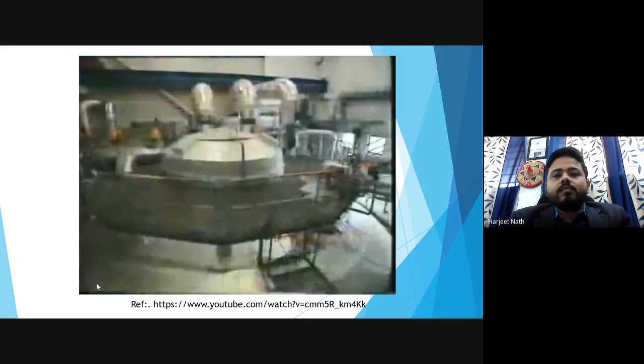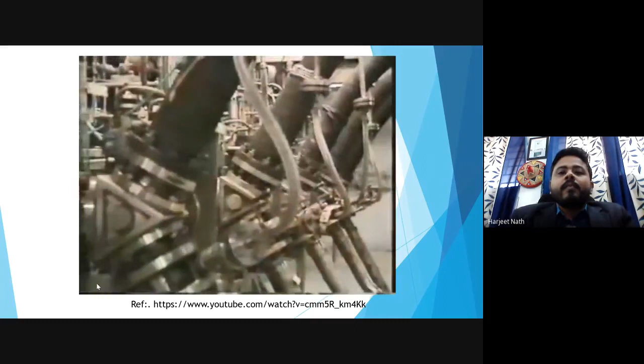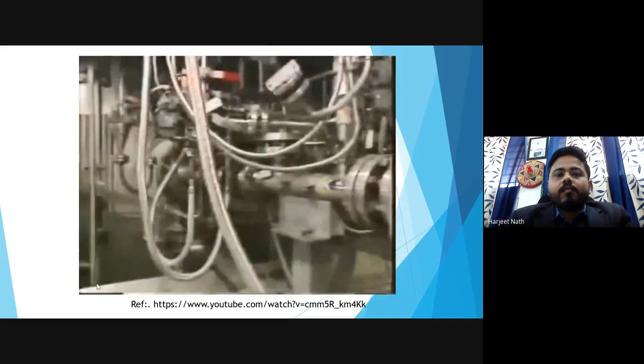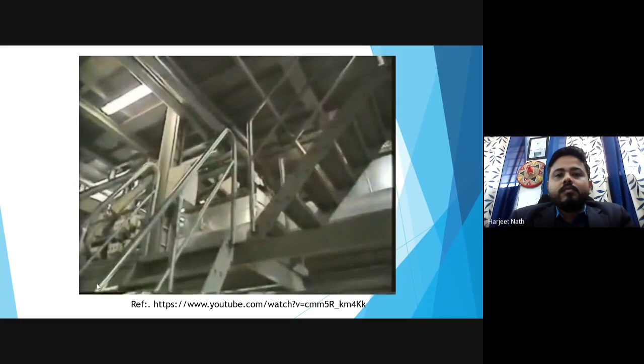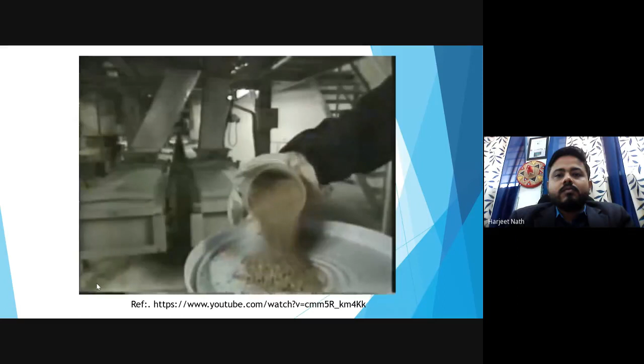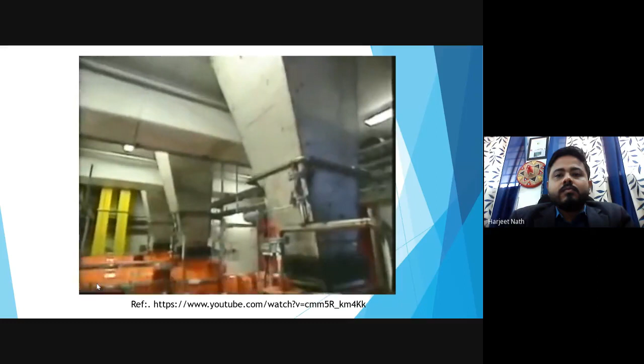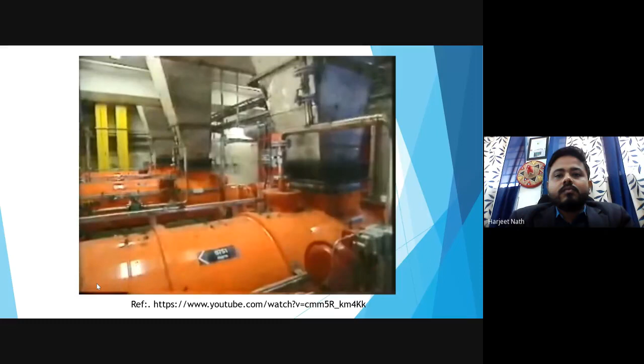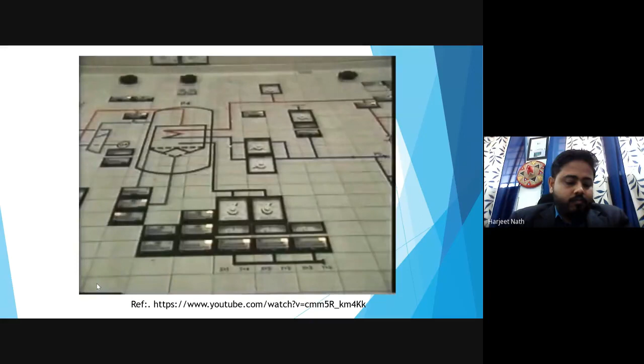FBC has several environmental advantages over conventional combustion techniques. Fluidized beds typically operate at around 800 to 900 degrees centigrade, below the temperature at which ash melts. This lower temperature also minimizes the formation of nitrogen oxides. Limestone mixed with the coal reacts with the sulfur oxides formed during combustion. Over 90% of the SOx formed can be removed. The solid residues can be used for road construction and landfill. FBCs are well suited to burning low-grade coals or those with a high mineral matter or moisture content. PFBCs using combined cycle electricity generation yield efficiencies of 46% or more, which means lower CO2 emissions.